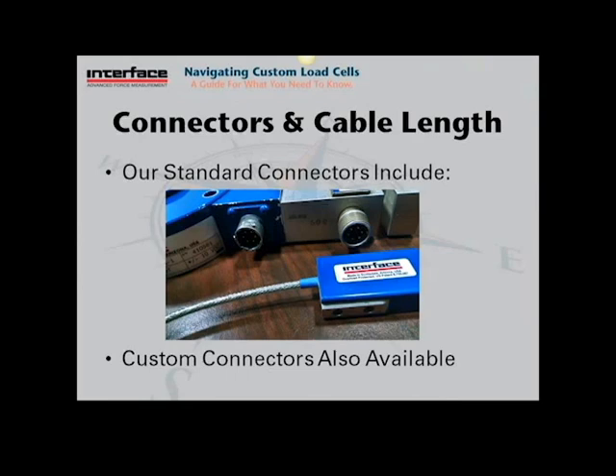The type of cable depends really on the application of the load cell and the size of the load cell. As far as custom connectors, we've supplied Lemo, Binder, Molex, and many other types. We have actual physical types, M12 metric connectors, which mate with a lot of popular industrial cables, such as Turck.